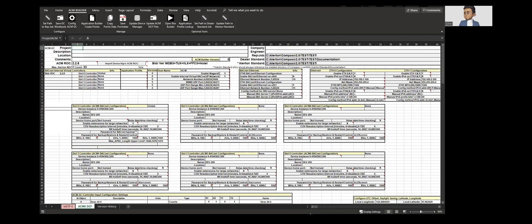Once this is ready, you could just go to update device manager and select add all BACnet devices in the active worksheet. You could do that or you could select particular devices and say add selected BACnet devices from active sheet. If you want ACM manager to be added you could select those as well by clicking the check mark here. Let's say add all devices. The total of 32 devices were added into device manager so the BACTalk.mdb file is updated.